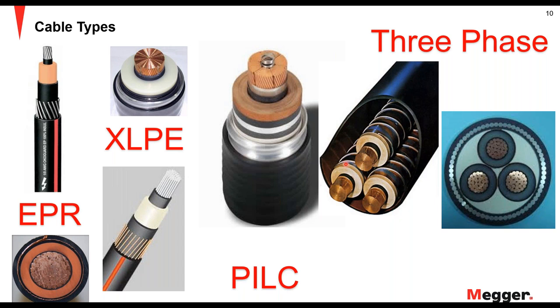Finally, you have your three-phase cables. On this one, you have individual shields on each cable — that's ideal for fault locating, because if it did fault out, it's going to go phase to ground in most cases, giving you a cleaner shot. If they share one shield, the disadvantage is that if it goes phase to ground you can get it pretty close, but if they went phase to phase you'll also have to test each phase to ground and each phase to phase combination to make sure you're covering the fault.